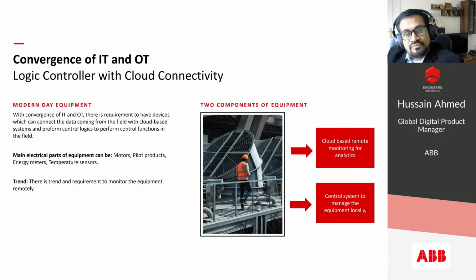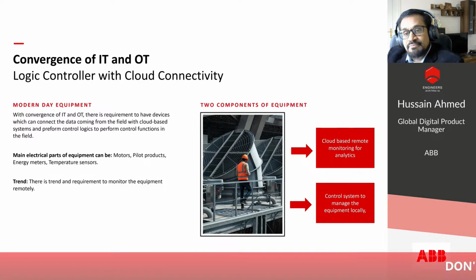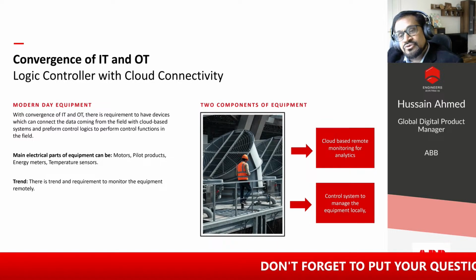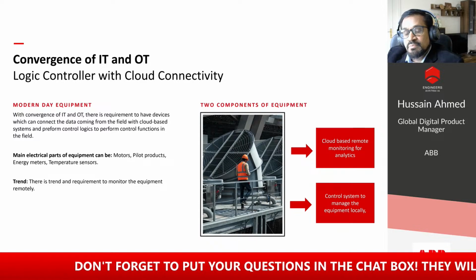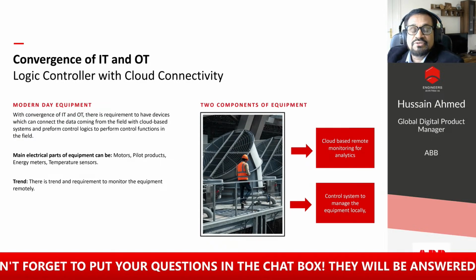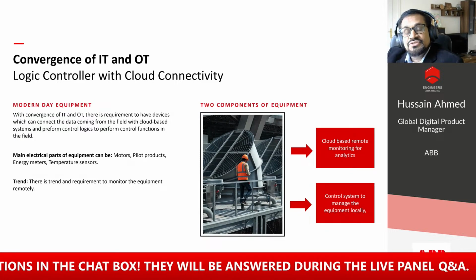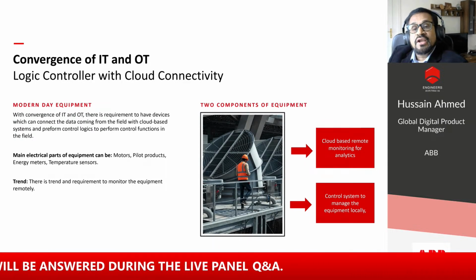With this, we need to understand that modern day equipment has two parts. One is connectivity to the cloud for better monitoring and analytics, and at the same time the classical control system is still there. We have to have a control system to manage the equipment locally - switching pumps and ventilators on and off subject to conditions like pressure, air, temperature, and so on. But at the same time, we have to ensure that this data is transmitted to the cloud-based system for better monitoring and analytics.